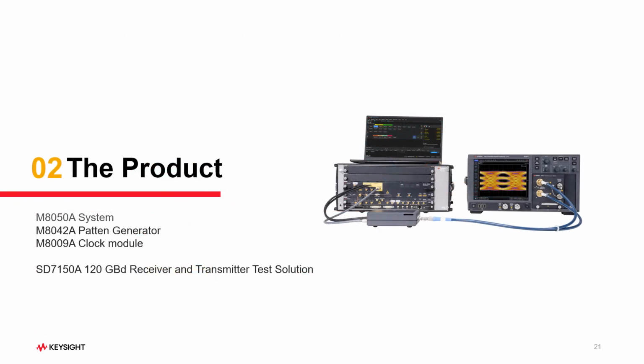Let us now dig deeper into the details of the new M8050A 120 gigabaud bit error ratio tester, or the BERT. The Keysight M8050A high performance bit error ratio tester enables the accurate characterization of receivers used in next generation data center networks and server interfaces.